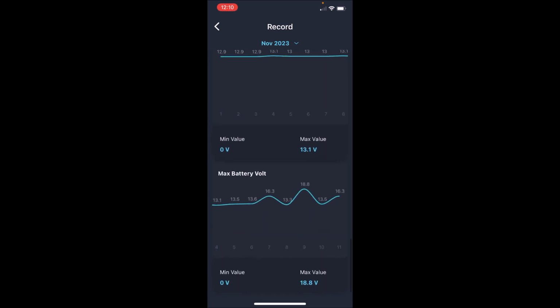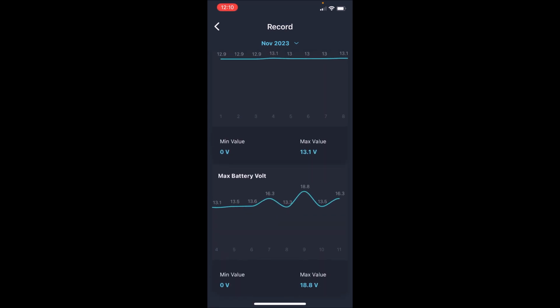...is, let's scroll on down here, these voltage spikes on the max battery volt. You'll see that on the 7th it registered 16.3, on the 9th it registered 18.8, and on the 11th today it registered again 16.3. There's some sun today, so the bank got full. And when the bank got full, instead of stopping at like 14.5, there was a voltage spike that went up, and this just recorded that spike. It didn't sustain at 16.3 or 18.8 for any period of time. It was just a spike, and the app recorded that spike.